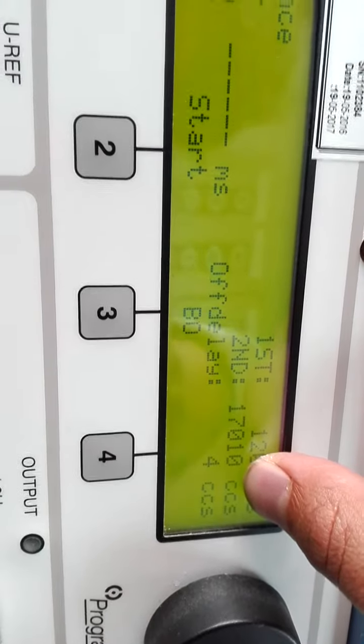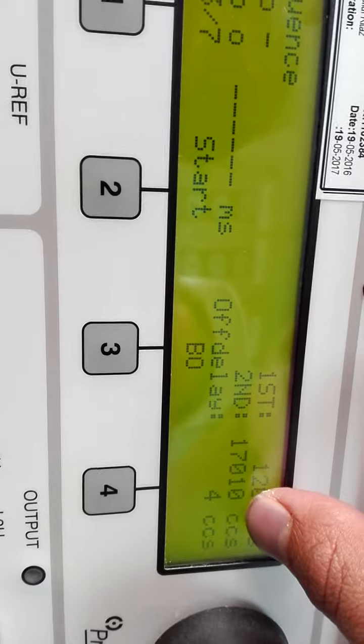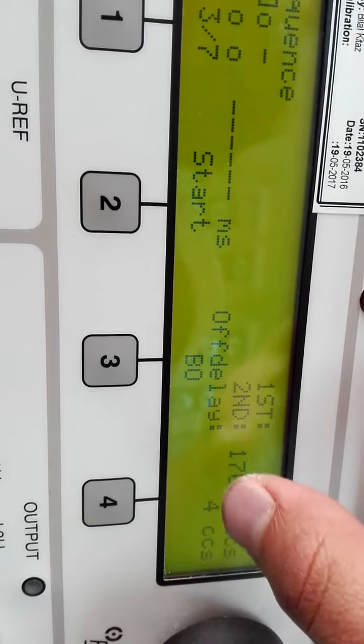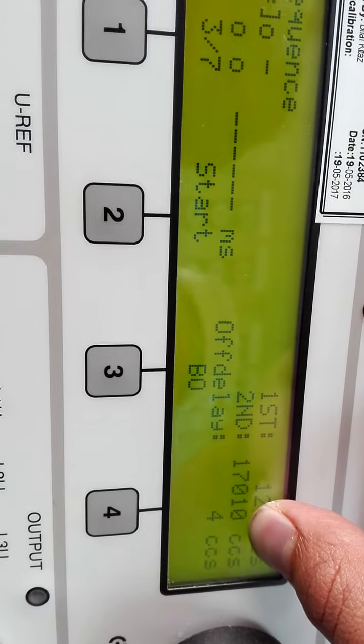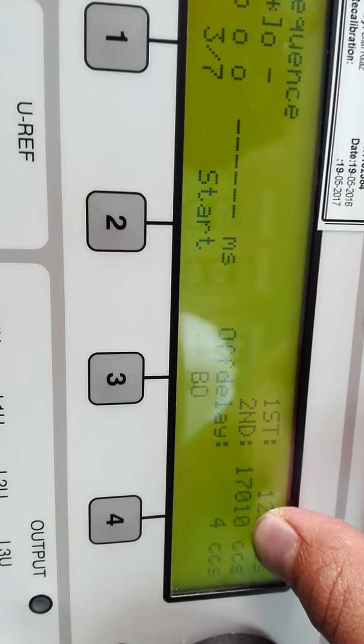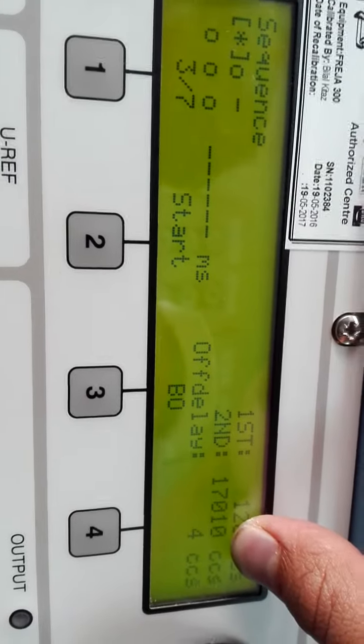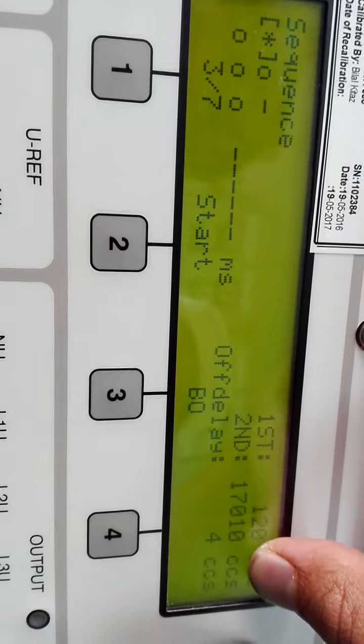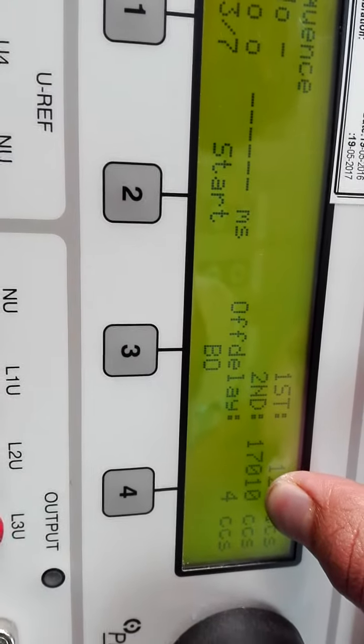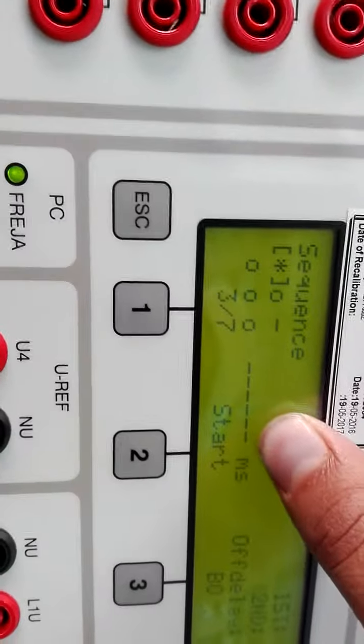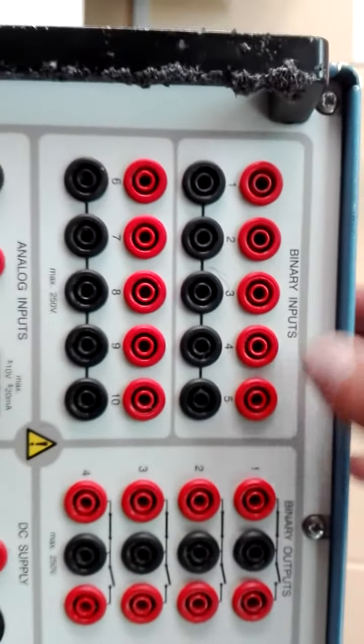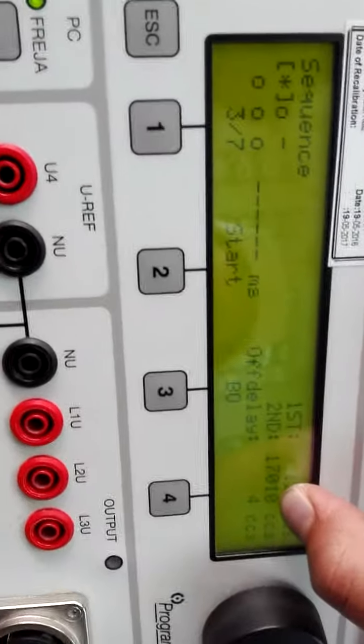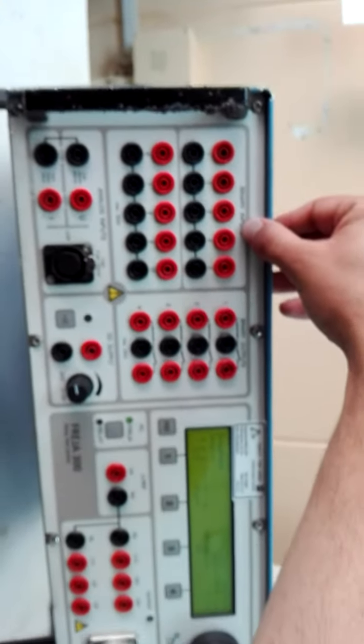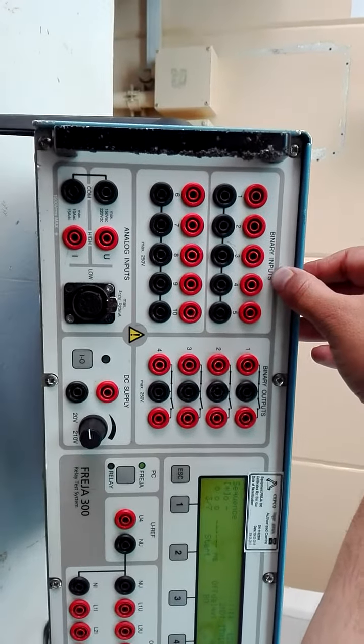So be sure, for example, if my timing measurement according to my settings I expect to be 10 seconds, I have to make sure that the cycles setting is more than 10 seconds. Because if I select, for example, 9 seconds, what will happen? My FREJA will get stopped after this point is reached. So no time will be measured here, because this time measurement is associated with my binary inputs. So my FREJA gets stopped by reaching this, not by changing the contacts from normally open to normally closed, or normally closed to normally open.